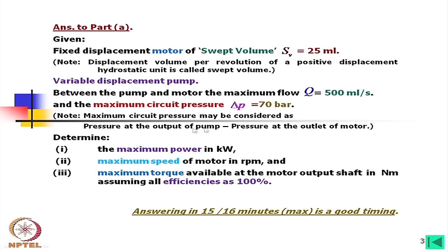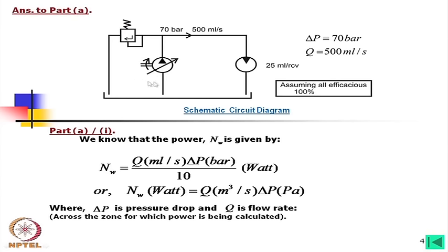The maximum circuit pressure can be considered as the pressure at the output of the pump minus the pressure at the outlet of the motor — in the ideal case assuming no loss in between. The maximum flow Q is 500 milliliters per second and circuit pressure is 70 bar. We draw a circuit diagram showing the variable displacement pump, fixed displacement motor, and pressure relief valve where pressure and maximum flow rate are marked.